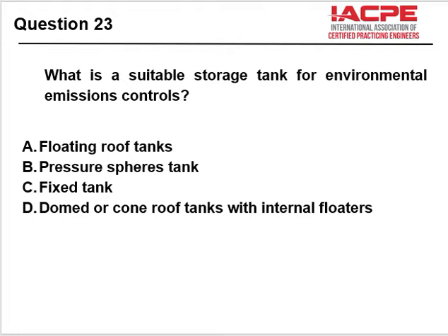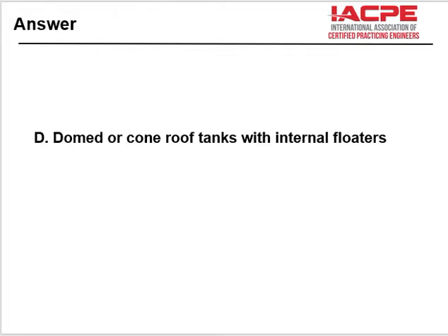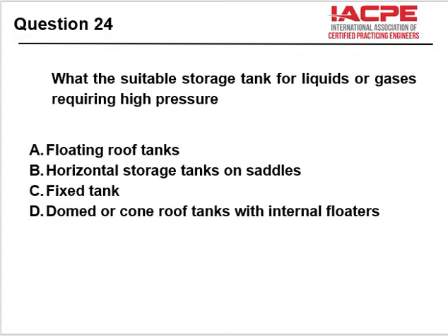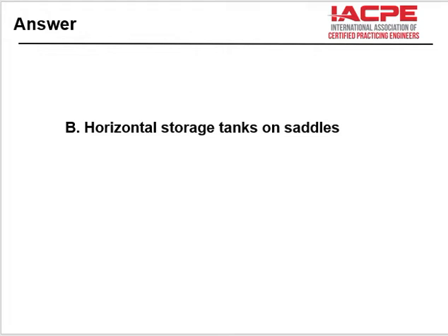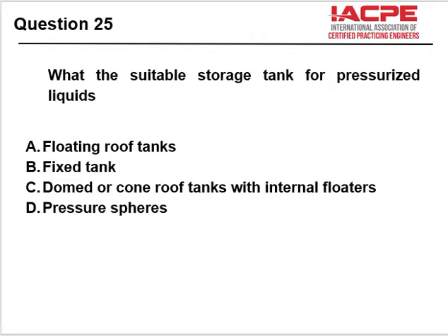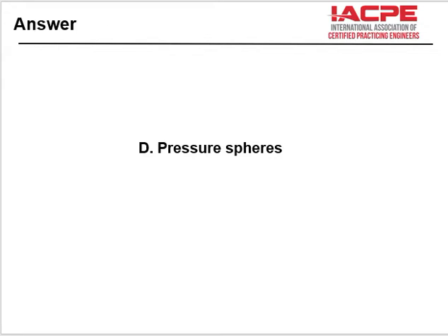What is a suitable storage tank for environmental emissions controls? Floating roofs, pressure spheres, fixed tanks, or domed or cone roofs with internal floaters. Domed or cone roof tanks with internal floaters. What is a suitable storage tank for liquids and gases requiring high pressure? Horizontal storage tanks on saddles. Sometimes these are called bullets. What is a suitable storage tank for pressurized liquids? Pressurized spheres.